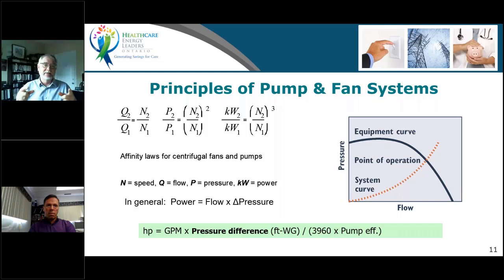That's a big difference, and that's a relationship that gets in your way when you're changing to more efficient motors that spin faster. A 1.1% speed increase, which may be a function of a stronger and better motor, ends up with a 3.5% power increase, and that can really kick you in the pants if you're not careful. So ultimately, we need to be aware of these rules. Now, most people have probably experienced these relationships firsthand.